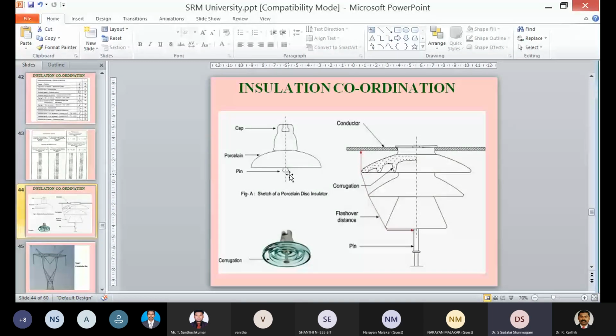Similarly, by this connection, if we go for a 220 kV system, the line to ground number of insulators will be roughly 14. So just by looking at the tower, now you can tell what is the voltage carried on the tower. I repeat, no need to look for any plate details. By counting the number of insulators, you can tell what is the line voltage available there.